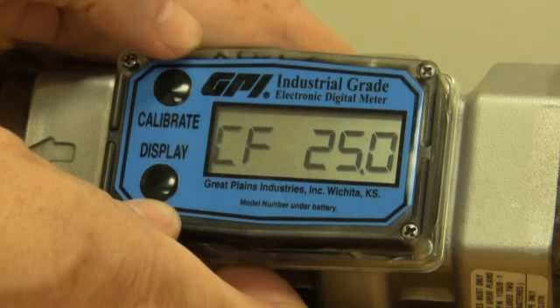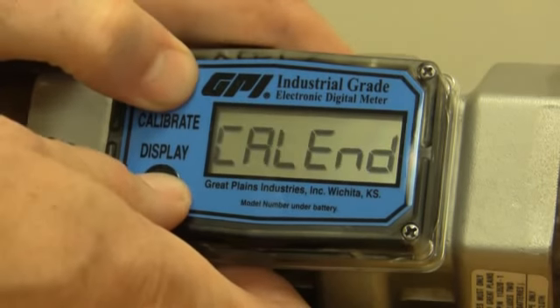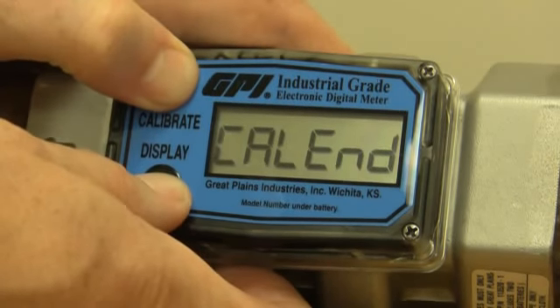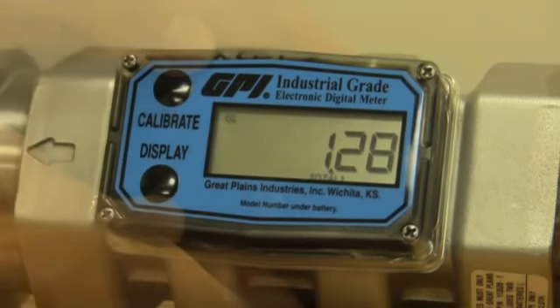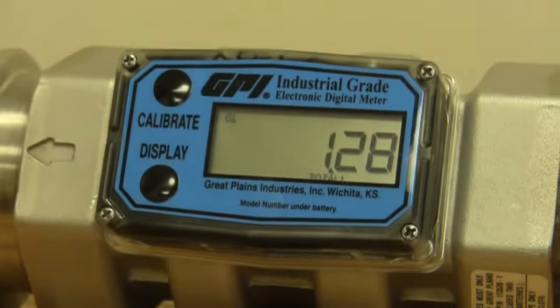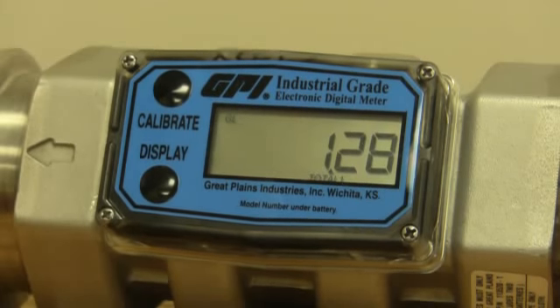Once you get your number in there, you hold down both buttons, and it says Cal End. Once you see that, you know you're finished. You can let go, and you're done. Now you notice it still says gallons, GL, but the word FAC is gone. So you know that you are no longer in the factory calibration, you're in your field calibration.